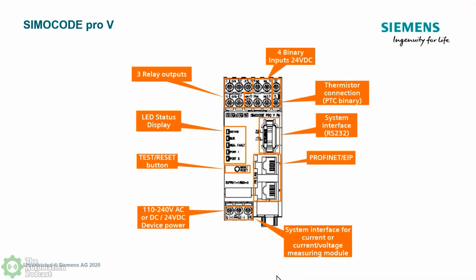It has 3 relay outputs that can handle up to 240 volts, 3 amps. Then it has 4 binary inputs, 24 volt DC. So that could be your handoff auto, your start stop switch coming to it. And then if you remember right there at the beginning, terminal block 8 is a 24 volt power supply, and you could wire all your inputs through that locally at the panel, nothing real far away.